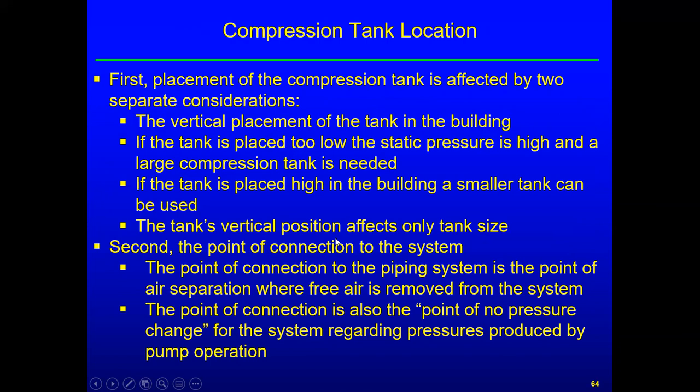So, location of the compression tank. It's affected by two separate considerations. One, vertical placement of the tank in the building. We've talked about that a bunch. If the tank is placed too low, the static pressure is high and we need a larger tank. If we put it high up on top, then we don't have the static pressure, so we get a smaller tank. Tank's vertical position affects only tank size.